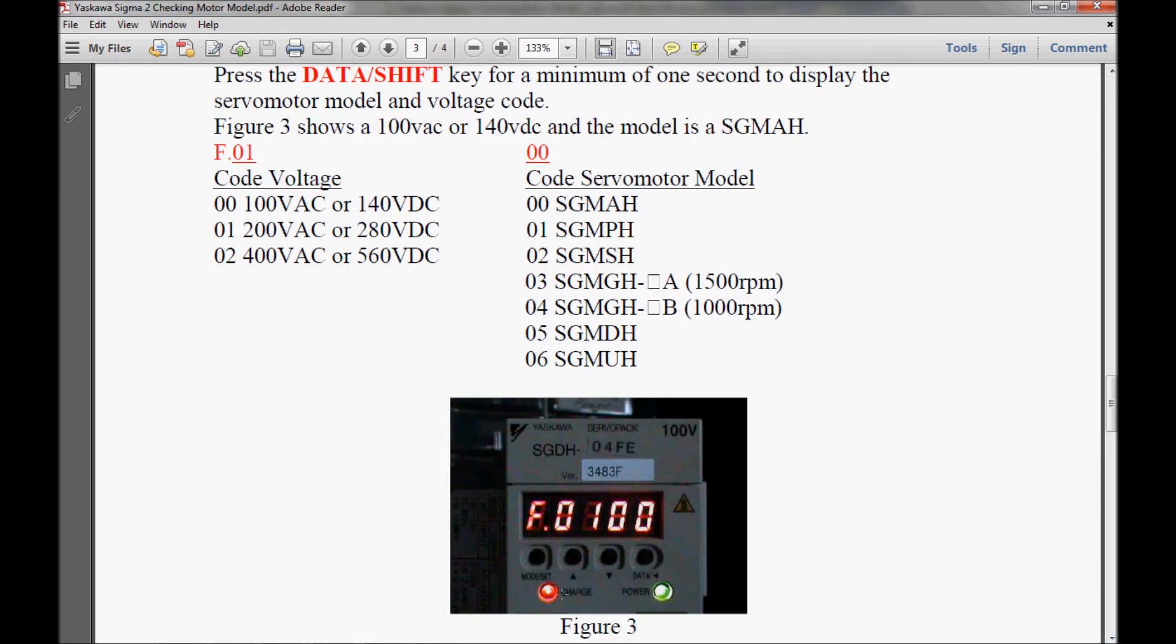In figure 3 here, I have a display of F.0100. So after the F.0, I have a 0.1. That is my voltage for the motor. So if I come over here to 0.1, that gives me a motor voltage of 200 volts AC or 280 volts DC. And then the next two numbers that I have here, 0, 0 in figure 3, give me a motor model of a SGMAH. So that seems simple enough.